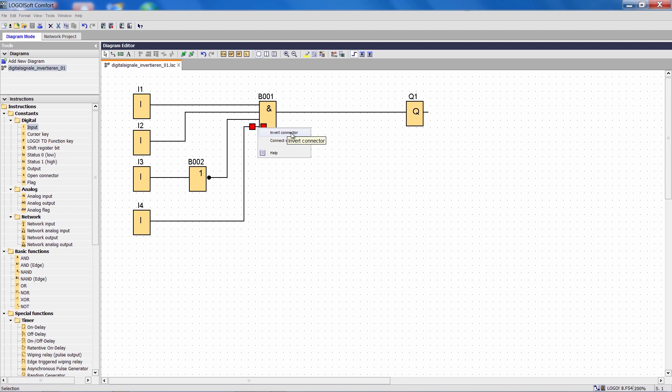The box that opens here allows me to invert the input. This is indicated by a black dot directly at the input. I can get the same result by double-clicking the input pin. The best thing about this method of inverting directly at the digital input is that I save one program block of storage capacity in the program memory.